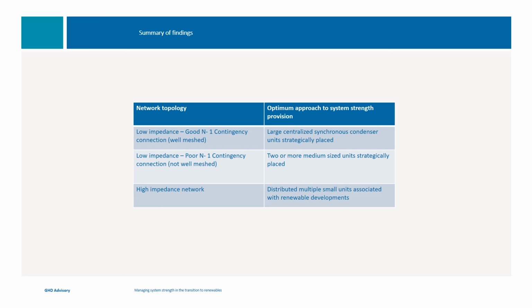This slide presents a summary of our findings from the study. We looked at different network topologies and then determined the optimal approach to system strength provision. For low impedance, good N-1 contingency, that is well-meshed network, such as the 275 kV backbone throughout most of Queensland, the optimal approach is to install large centralized synchronous condensers strategically placed. For low impedance but poor N-1 contingency, that is not well-meshed networks, 2 or more medium-sized units strategically placed provides the optimum solution. And finally, for high impedance, low voltage networks, distributed multiple small units associated with renewable developments represents the most economic approach to providing system strength.